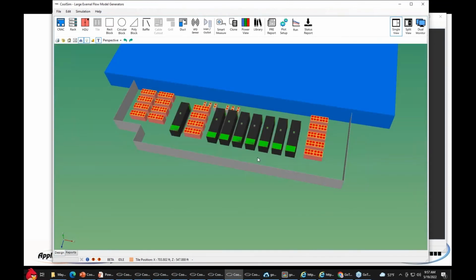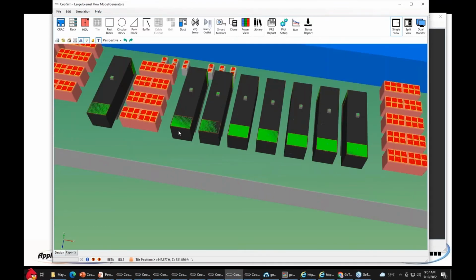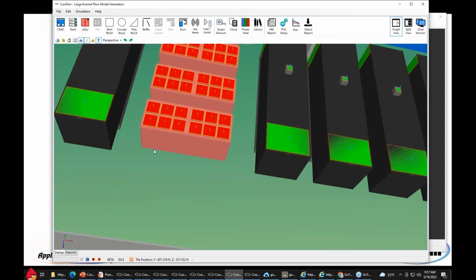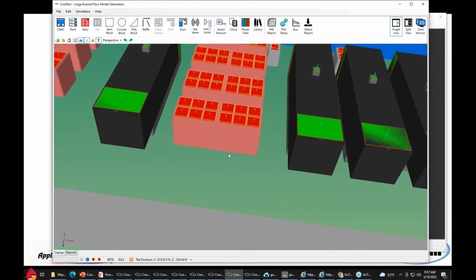This one is sitting in what are sometimes called data yards. I don't know what they're called internationally. They can be many things, but here we have heat exchangers over here. These are condensers, typically, and then we have the generators sitting in between them. Not an unusual situation, but the problem is these generators, condensers, behave in a way that if the inlets get too high, the cooling capacity of them drops off very quickly.